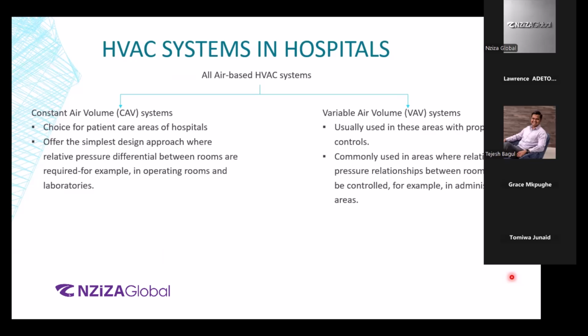Now, as I mentioned, this comes in very handy when you have to do some kind of pressurization, right? When we spoke about pressurization in the operating room, in the restroom, and so forth. So wherever you have a pressurization that you need to maintain between a room and the given adjacent areas, constant air volume will be what is preferred, right? So these are the 2 broad classifications for an all air-based system.